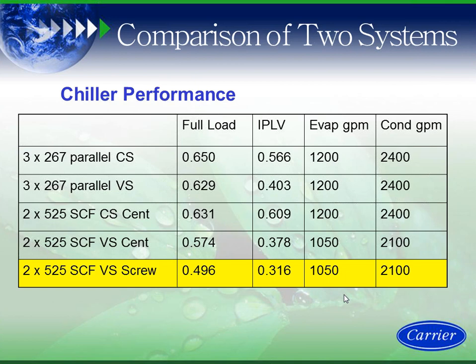And then I have 2 series counterflow centrifugals, constant speed, 2 525 ton series counterflow centrifugals, variable speed, and then I have the 2 525 ton series counterflow variable speed screws, full load, part load. Okay, when you're looking at from an engineer and an end user, when you hear basically the terms of 0.629 full load and 0.403 part load for a chiller plant, you basically be very excited about those efficiencies.